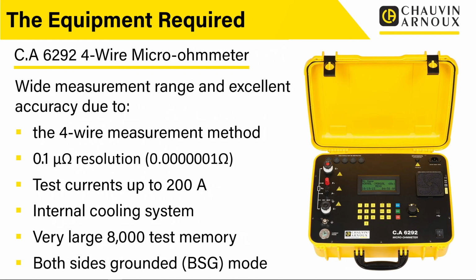So it's really, really accurate. You're going down to 0.1 of a micro ohm resolution. So we're really getting into those high levels of accuracy. As we said, test currents up to 200 amps. It's got its own internal cooling system, which is what allows it to actually carry on doing these tests time after time after time. Large 8,000 test memory.